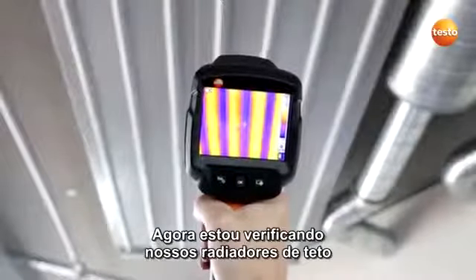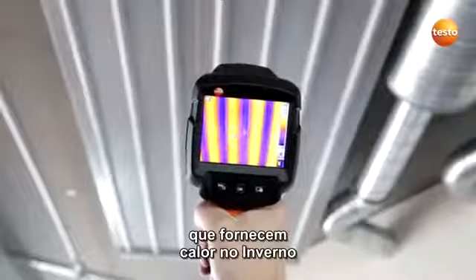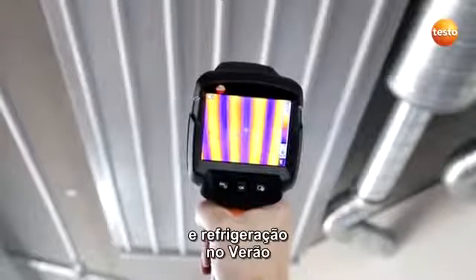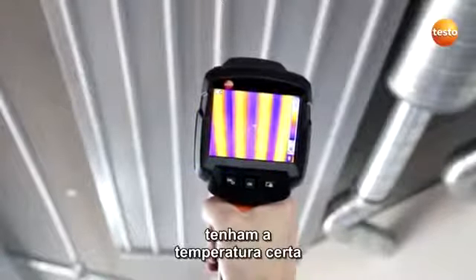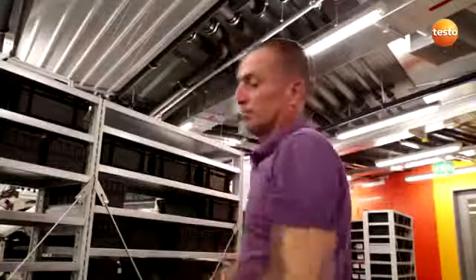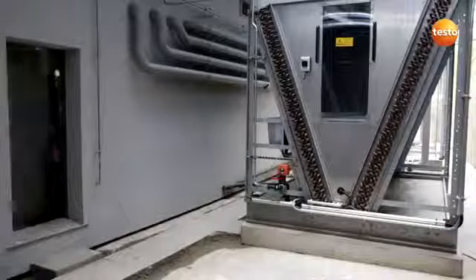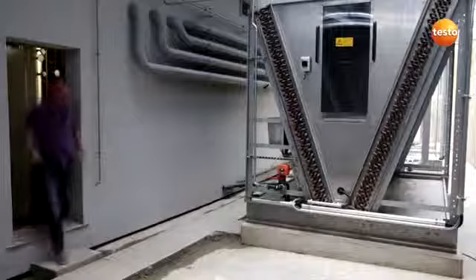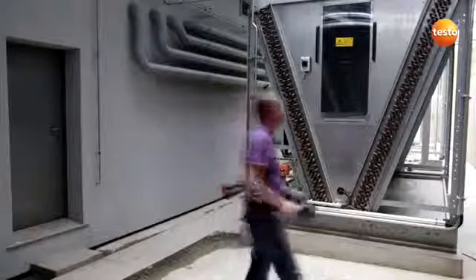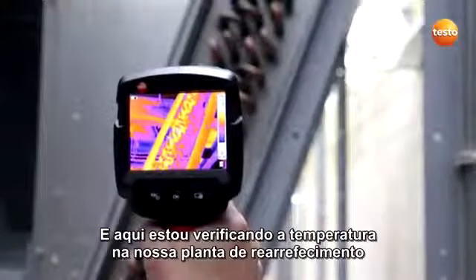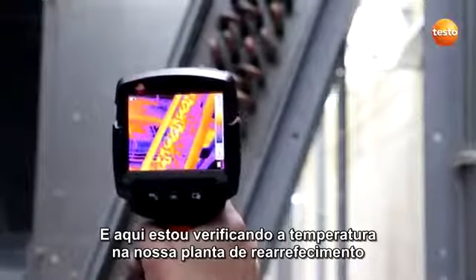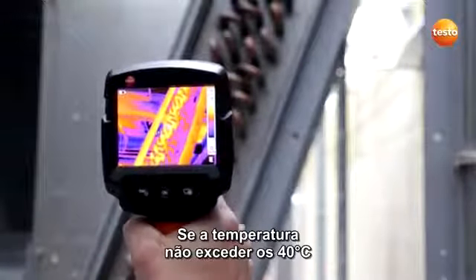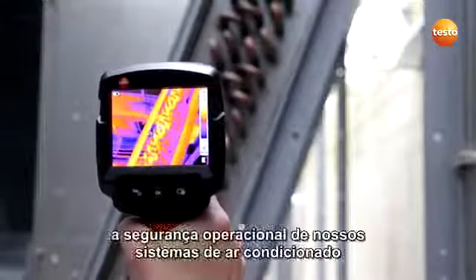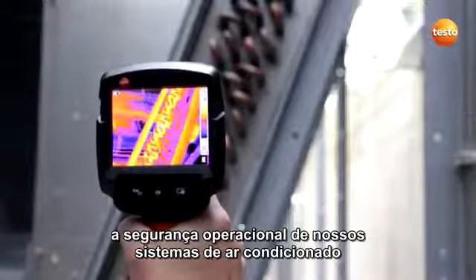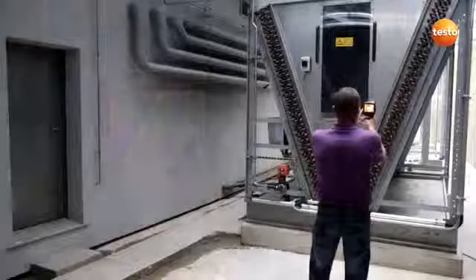I'm now checking our ceiling radiators, which provide heat in the winter and cooling in the summer, so that our production rooms have the right temperature. And here I'm checking the temperature on our recooling plant. If the temperature doesn't exceed 40 degrees Celsius, the air conditioning system's operational security is guaranteed.